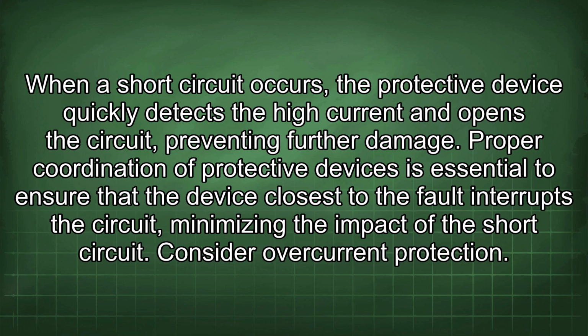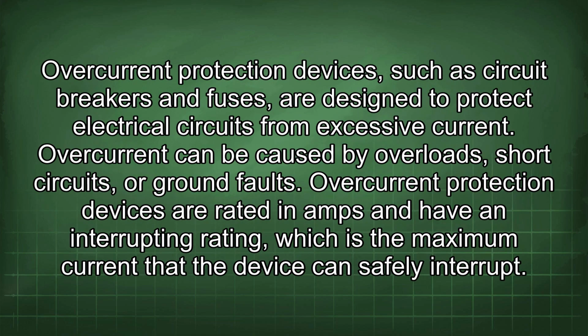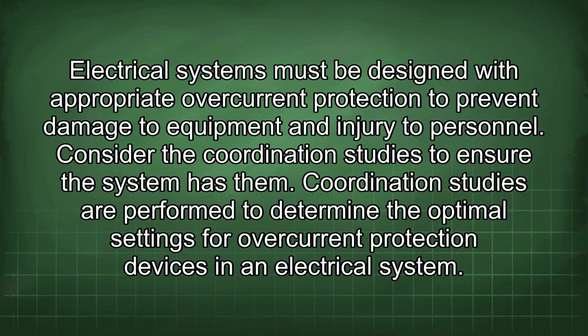Consider overcurrent protection. Overcurrent protection devices, such as circuit breakers and fuses, are designed to protect electrical circuits from excessive current. Overcurrent can be caused by overloads, short circuits, or ground faults. Overcurrent protection devices are rated in amps and have an interrupting rating, which is the maximum current that the device can safely interrupt. Electrical systems must be designed with appropriate overcurrent protection to prevent damage to equipment and injury to personnel.